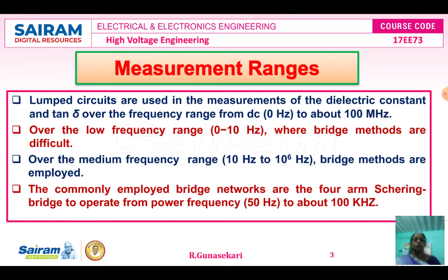The Schering bridges are commonly employed for the higher power frequency range, that is 50 Hz to about 100 kHz. The high voltage Schering bridges are used for the power frequency measurement, that is 50 Hz, when the voltage effect or stress on the dielectric constant and loss factor tan delta is required. The bridge circuits present problems in shielding, and the measurement errors become excessive for the high frequency range, that is 100 kHz to 100 MHz.